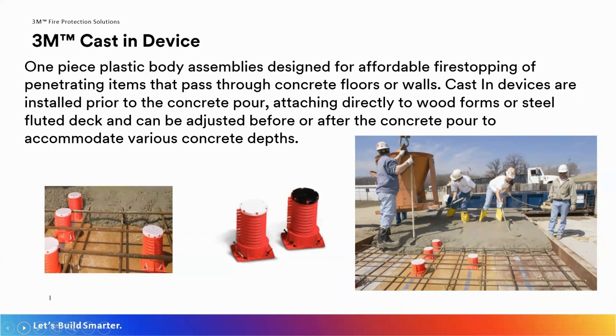For most of our fire stop systems with these, typically there's no other products used other than occasionally will require some mineral wool that has to get stuffed inside the steel or the plastic sleeve. So again, these would get attached directly to either wood formwork or steel formwork. They get left in place. There is a plastic cap over the top of the sleeve so that concrete doesn't fill the inside of the sleeve. And there's also pull tabs on there so you can set to the thickness of your floor or your wall. Next slide.